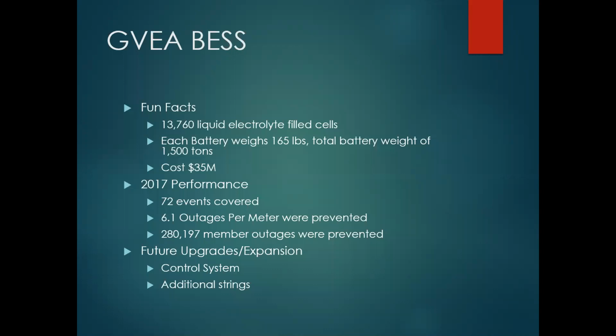That's roughly one event every 5 days, that's pretty significant. Yeah, when you actually look at how much it's putting out, it is significant. So it responds to system events on a frequency power curve. Some of those events are down in Anchorage, where an Anchorage generator tripped, which would cause a reduction of power transfer capability up north. So it kicks on until they can hit start on the North Pole turbines.